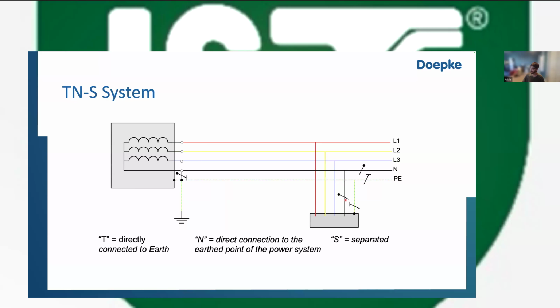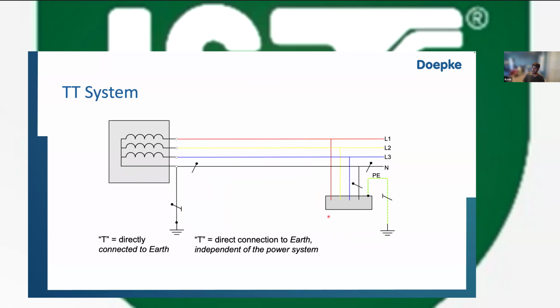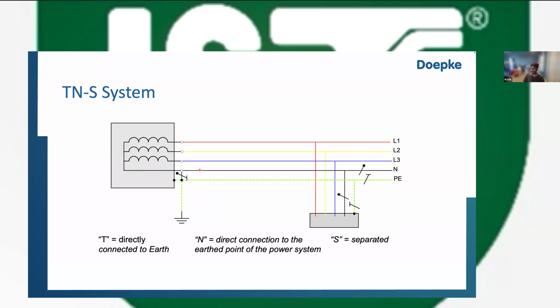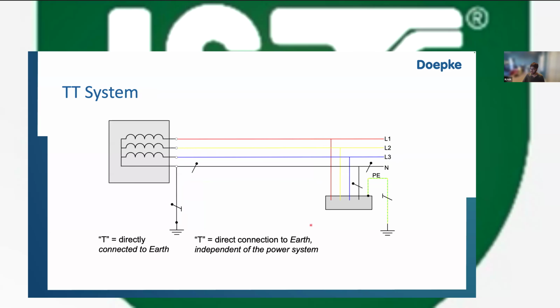Now, what you will realize is if you have a fault here between the body and the phase, let's say L1, the amount of current that will flow through is very high. It is similar to a short circuit, because you have a very negligible amount of impedance. There are many TN systems: TNS, TNCS, TNC. But what I want to focus on is just the TN part, which is that if you have an earth fault, there is a lot of current that flows through, enough current to cause interruption, maybe an MCB or a fuse, etc.